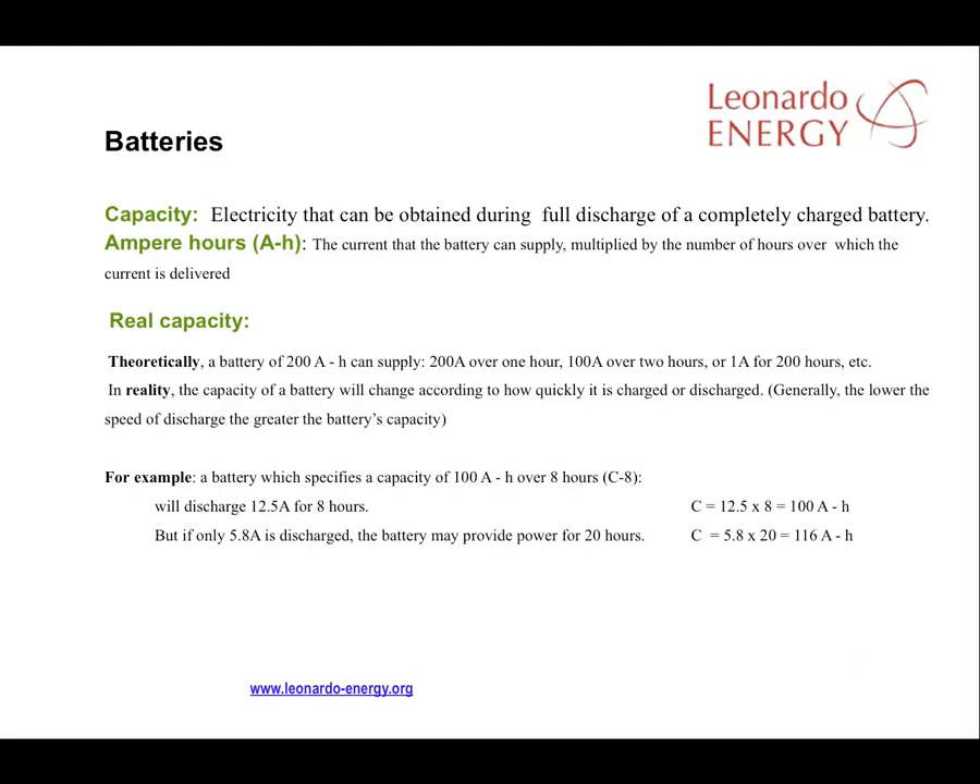Here are some of the considerations when designing an off-grid facility. First, battery capacity. Battery capacity is defined as the electricity that can be obtained during the full discharge of a fully charged battery. The capacity in ampere hours is the current that the battery can supply multiplied by the number of hours that it can deliver that current, referred to a certain voltage. For example, a battery of 200 amp-hours and 12 volts could theoretically store 2,400 watt-hours.